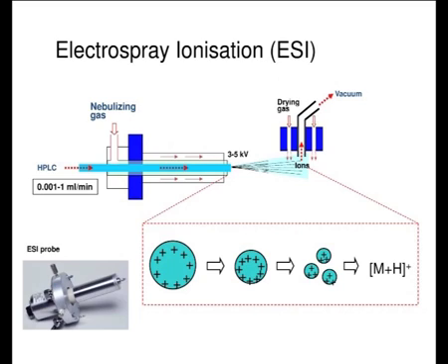Let us see ESI, the electrospray ionization technique. In this case, there are two concentric capillaries. From the middle capillary, there is a flow of the liquid or mobile phase coming from the HPLC. From the outer capillary, there is a flow of the nebulizing gas. Here we are using nitrogen as the nebulizing gas. At the tip of the capillary, we apply a high voltage between 3 to 5 kilovolts. What happens? Because of the nebulizing gas, it is nebulized into fine droplets, and because of the high voltage, it forms charge, either positive or negative, but it forms a single type of charge.